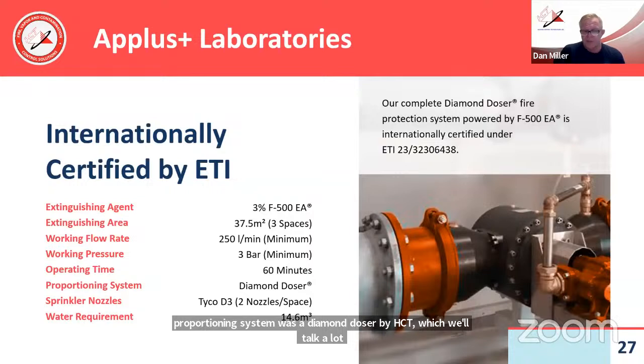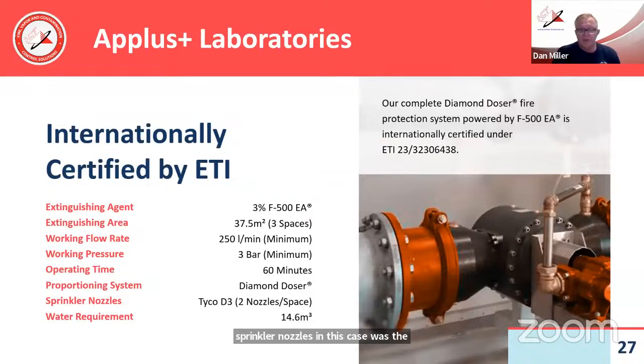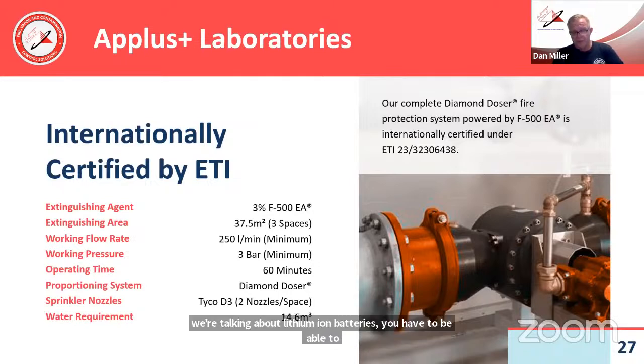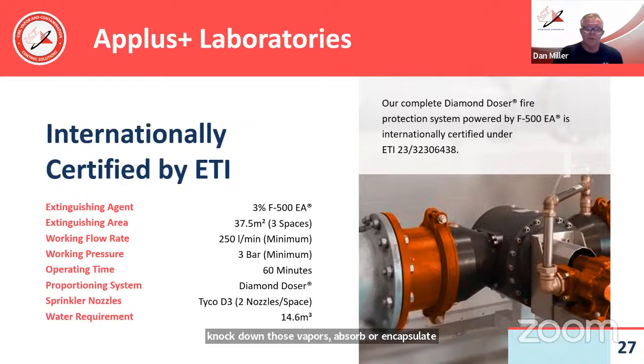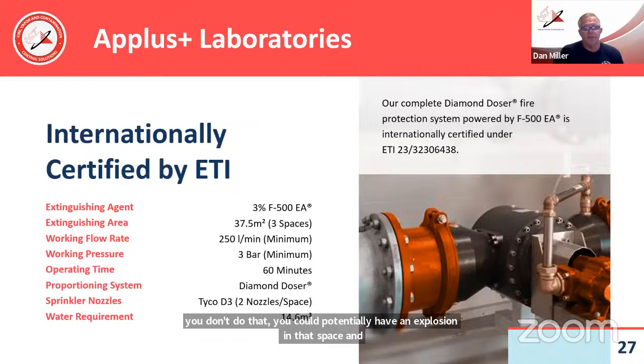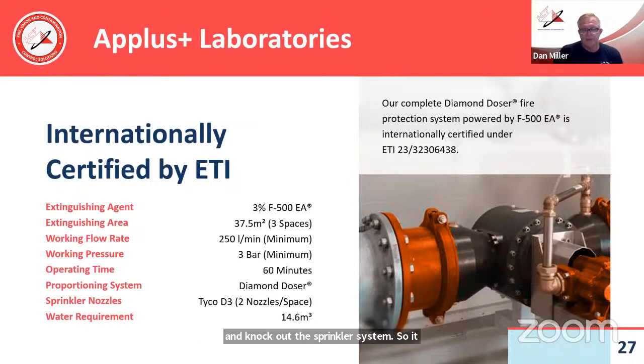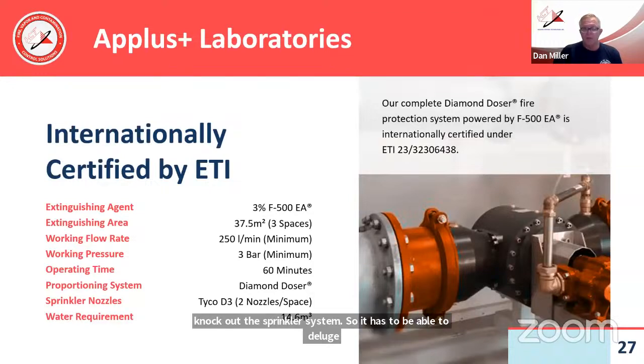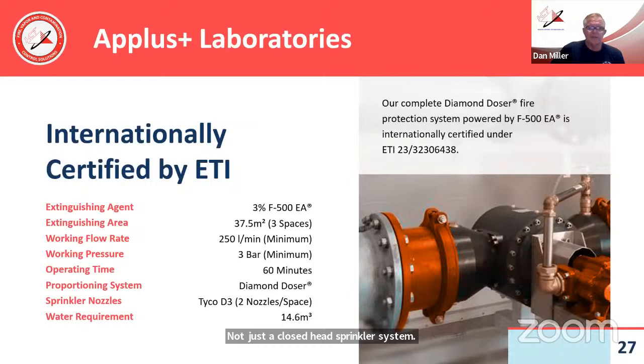Sprinkler nozzles in this case was the Tyco D3, 2 nozzles per space, and they are a deluge nozzle, which is very important when we're talking about lithium-ion batteries. You have to be able to knock down those vapors, absorb or encapsulate those vapors in a situation where you have a vapor only thermal runaway. If you don't do that, you could potentially have an explosion in that space and knock out the sprinkler system. So it has to be able to deluge, not just a closed head sprinkler system. Water requirement was 14.6 cubic meters.